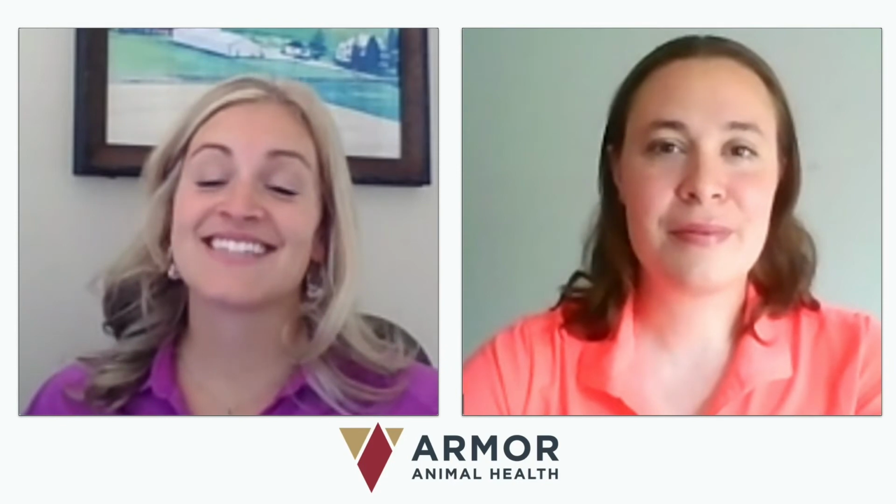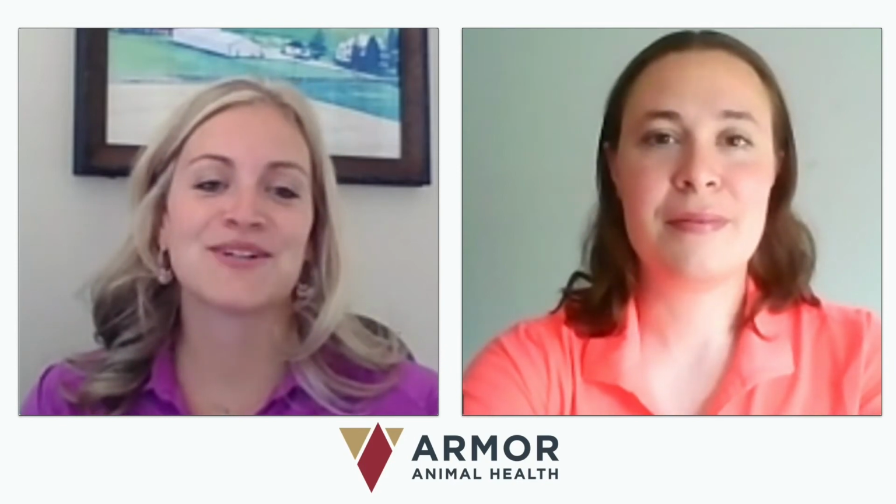Now it is definitely a two-person job because one person needs to be fogging the barn. So they will stand outside where the fan inlet is. And then another person will be inside the barn watching to see where that air is going, making sure that the barn is clearing that foggy air the proper number of times per hour. Yeah, like Dr. Vicky said, it's definitely a two-person job.